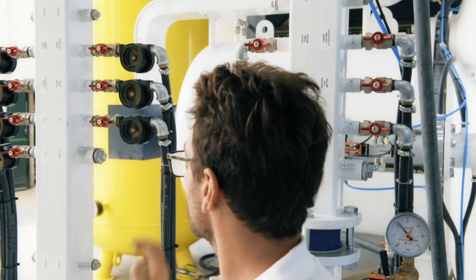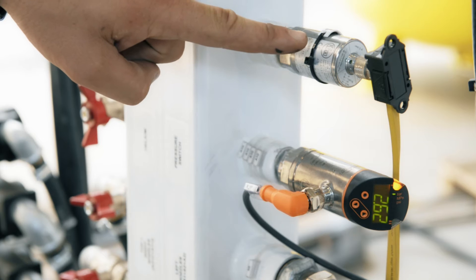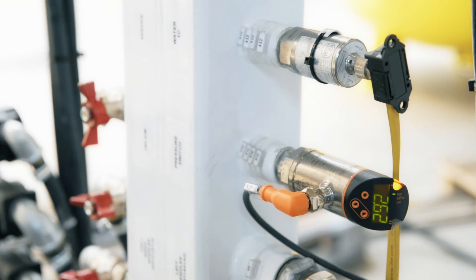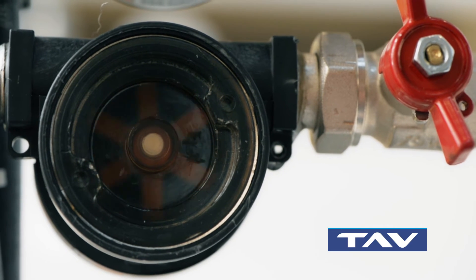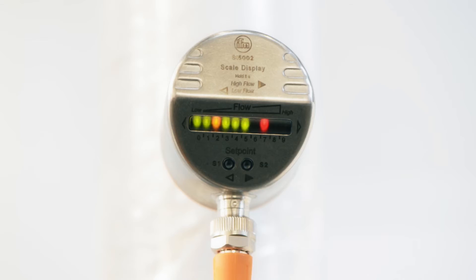It is critical to calibrate the flow of each utility by monitoring the water temperature and working pressure. Mechanical flow indicators allow you to monitor the actual water flow through the pump wheel movement. Electronic sensors offer a visual indication of flow speed through LEDs, which can also indicate an interruption of water flow. Electronic flow sensors placed on the most important circuits are able to provide an alarm signal to the control panel in case of an interruption or decrease of water flow below the threshold.